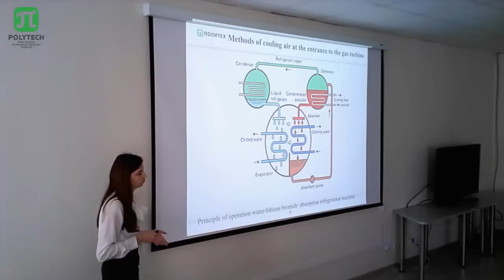The possible sources of thermal energy are steam, hot water, and waste heat gases. But in our case, we can't use waste heat gases, because the minimum temperature for operation of an absorption refrigerating machine should be 300 degrees, but we have only 100. Steam from the low pressure drum of the heat recovery steam generator and hot city water were chosen as possible sources of thermal energy. I calculated the cooling capacity, which equals 11 megawatts. There are many companies that produce absorption refrigerating machines, and I chose, for example, one from St. Petersburg, named Energia Holodra. From the catalog of production, I chose an absorption refrigerating machine on hot water and two on saturated steam.